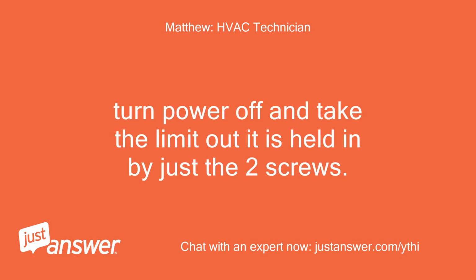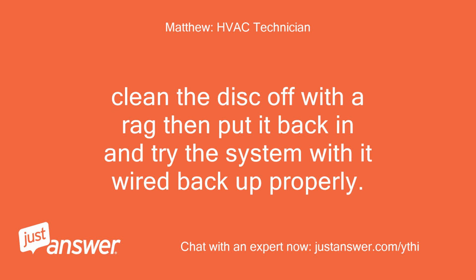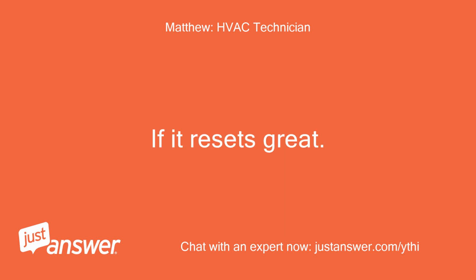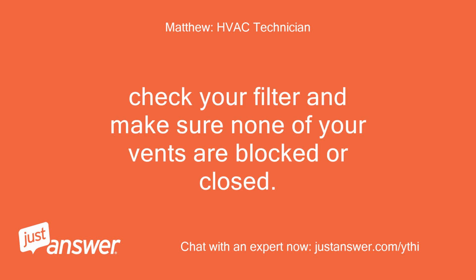Turn power off and take the limit out. It is held in by just the 2 screws. Clean the disc off with a rag, then put it back in and try the system with it wired back up properly. If it resets, great. Check your filter and make sure none of your vents are blocked or closed.